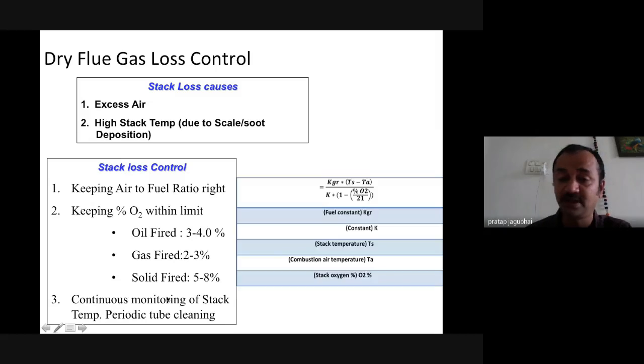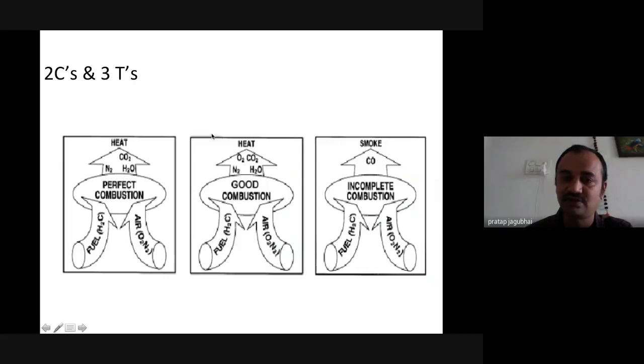8% for the oxygen. So this is the formula which I have told you very theoretically: delta T, the stack temperature minus the ambient temperature, which leaves through the chimney in the form of stack temperature. The lesser the delta T and the lesser the excess air, that is 21 upon 21 minus O2, the lesser the dry flue gas loss. So the lesser the excess air and the lesser the delta T, the more we minimize the dry flue gas loss.